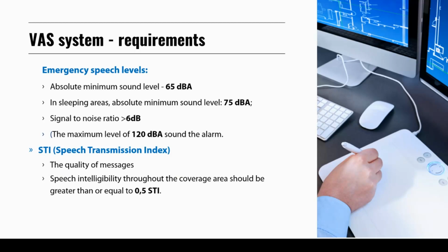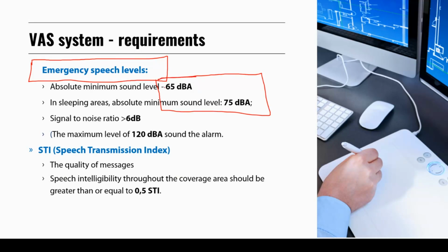pressure level, or SPL. That is the level of the audio signal that can be heard by the people inside the building. So we need to make sure that the voice alarm system is covering all public areas where people can be present, and that the level of the audio signal, the sound, is loud enough for all people to hear it, so that nobody is left out in an emergency situation. So we need to make sure that all areas are properly covered with sound with a minimum loudness. So there are absolute minimum levels that are required in voice alarm planning.